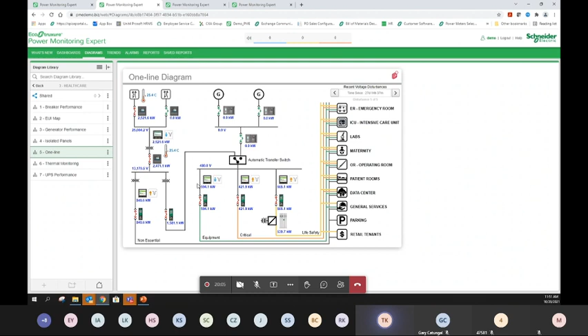So, in the standard SCADA or BMS system, alarms are normally, okay, before I say so, sorry. Electrical alarms are correlated to one another. It means that the first fault is followed by the second fault, followed by the third fault. So they are all correlated to one another in the electrical system, of course, and in other systems. But in our software, the alarms will not show, let's say, 10 alarms correlated to one single topic. The software will not show you 10 alarms. It will show you only one alarm: 5 alarms or 5 equipment are affected. This is how the software will do it automatically.